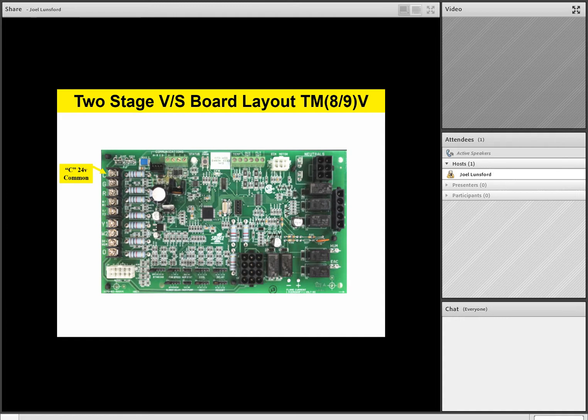So C is 24 volt common. G is our fan command from the thermostat for fan operation. So G is for fan. R is 24 volt hot. That's what powers everything up on the 24 volt side. So R will be taken up to the thermostat to power up the thermostat and to provide the control voltage for all the thermostat functions.